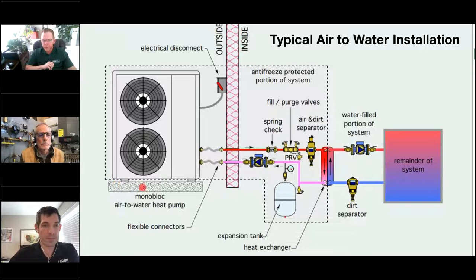The other thing we've got to pay attention to is the defrost cycle. So when this unit does defrost, we want to make sure that we don't just have that sticking out over the edge of the unit, unless your intention was to put a skating rink beside your house. If you're right next to your neighbor, you may also have a skating rink followed up with a lawsuit. So we need to make sure we pay attention to that. Make sure we have good separation between the actual house and the outside wall. We want to have good air movement through that unit, just like with any air source heat pump.